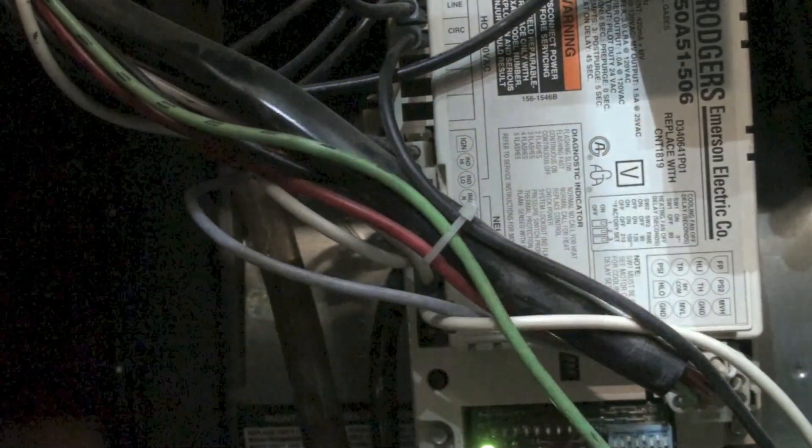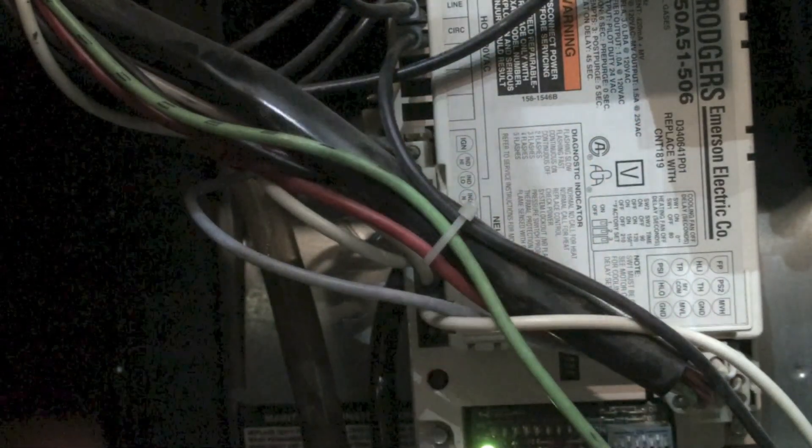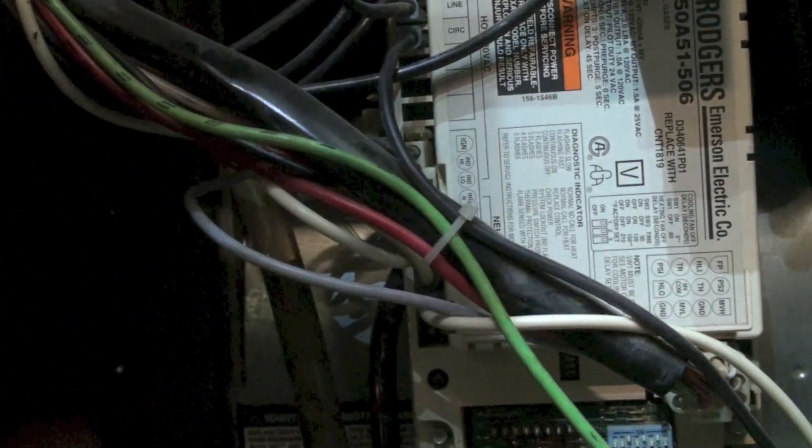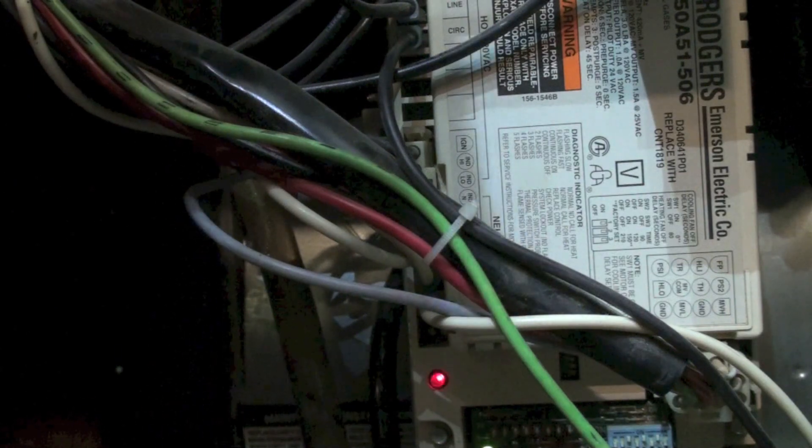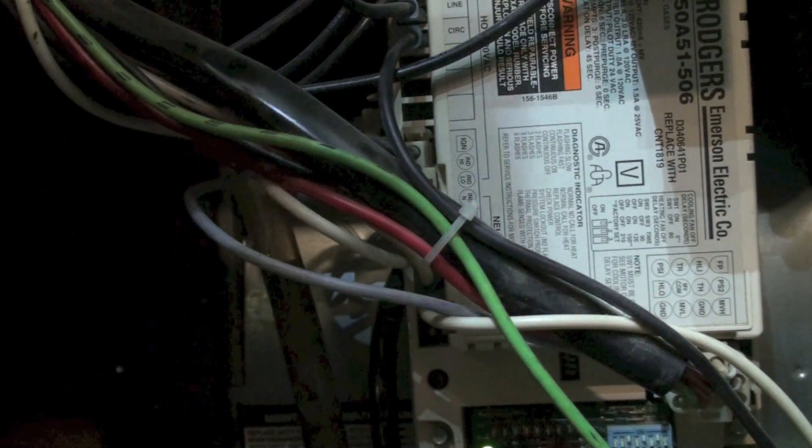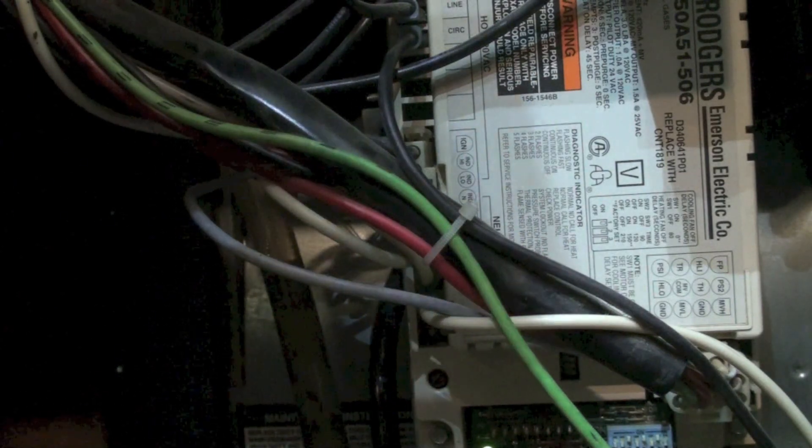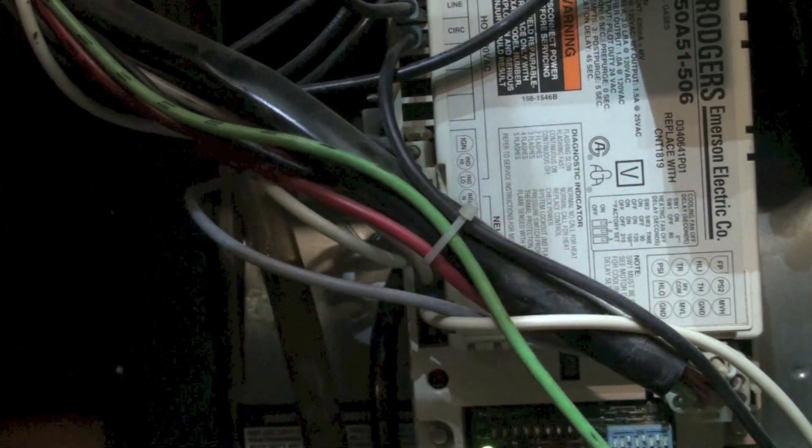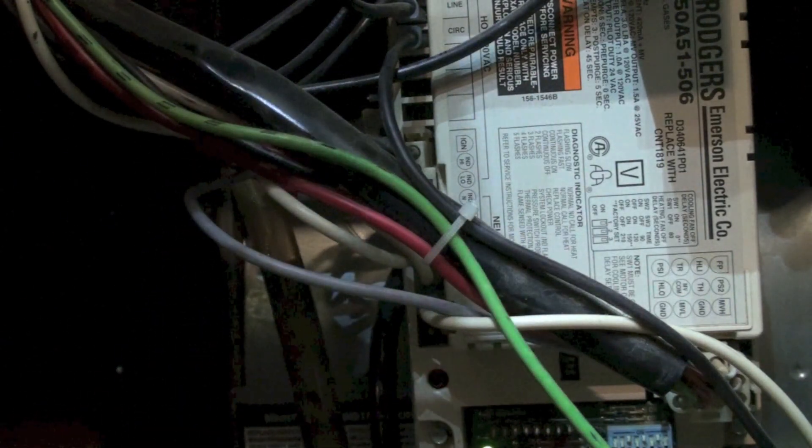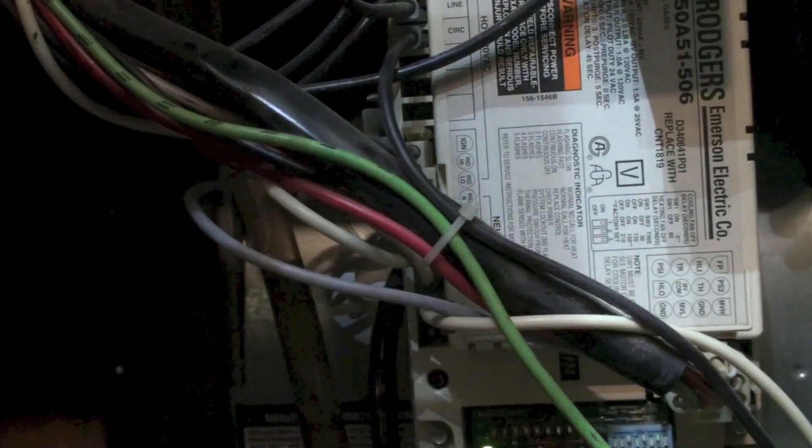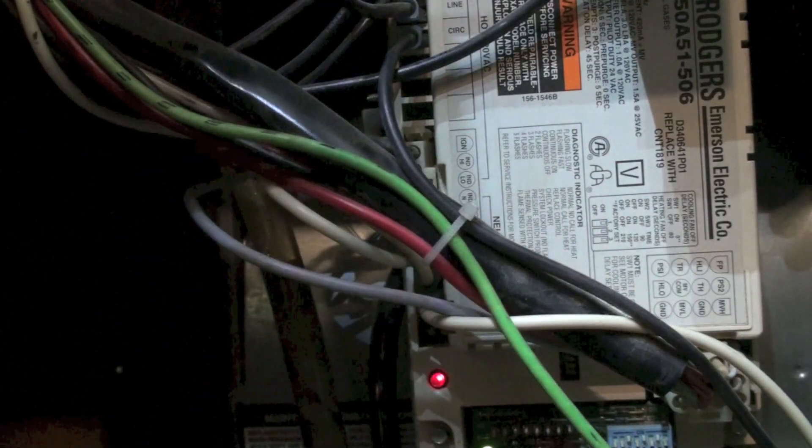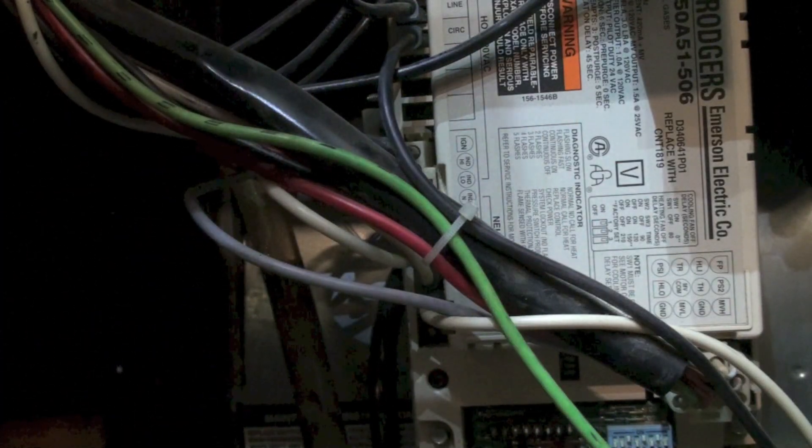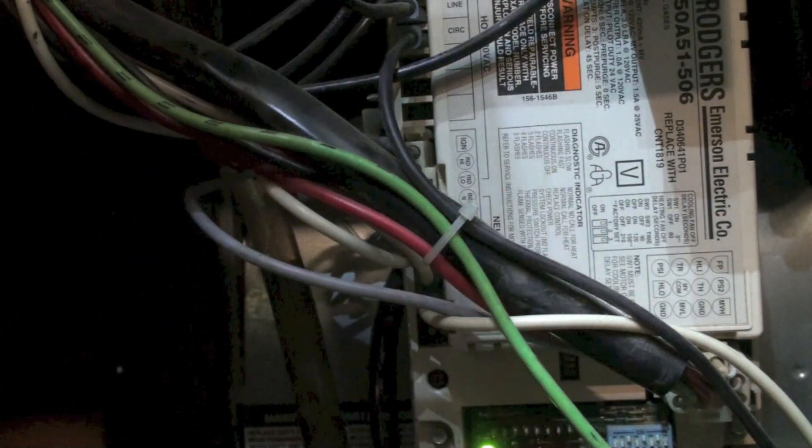Okay, this one here, the four blinks, that means a temperature switch is open. This could be a rollout switch, this could be a limit switch that's sensing the temperature inside the furnace. There's a number of things it could be.